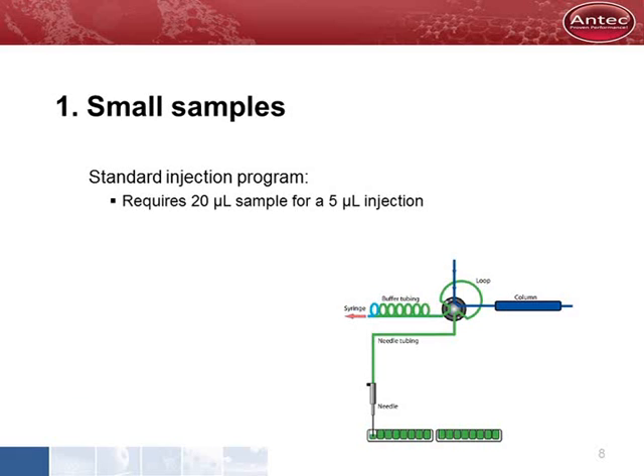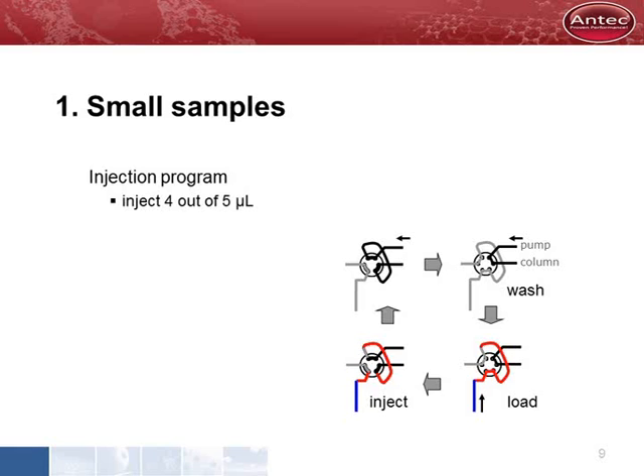Our first requirement is about working with small samples. A standard injection cycle to fill a 5 microliter loop uses about 20 microliter sample to fill the injection flow path. We developed an injection program that enables us to inject 4 microliter out of 5 microliter sample in a reproducible way. Instead of filling the entire sampling flow path, we pick up a small volume and move that to the injection loop.